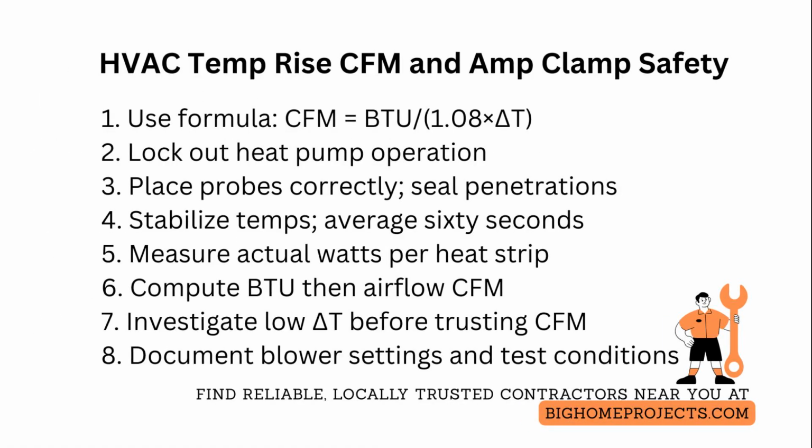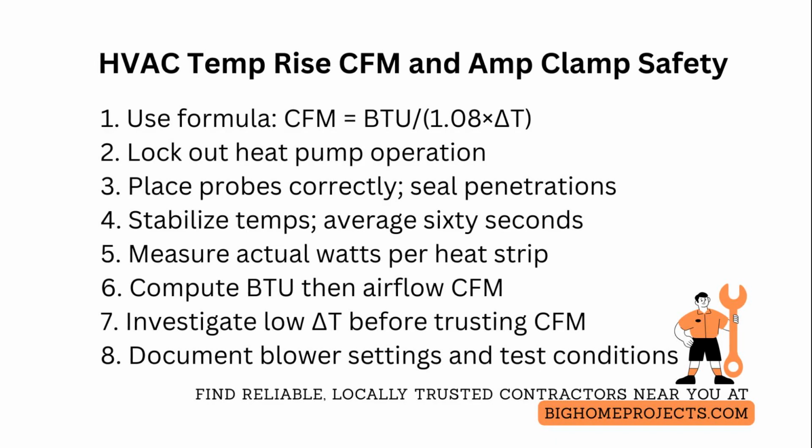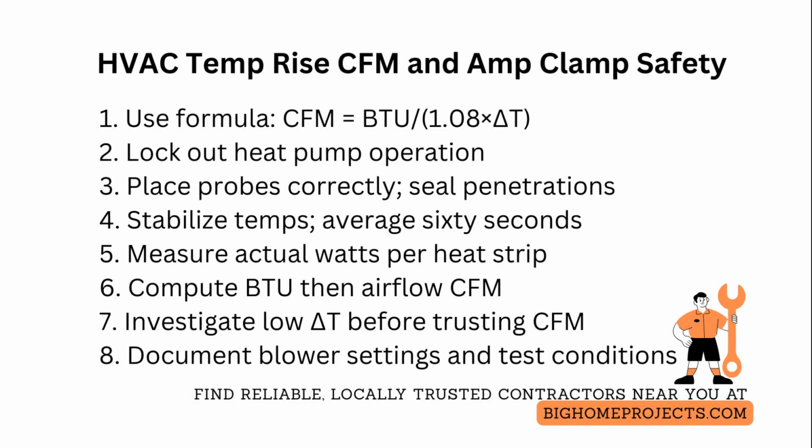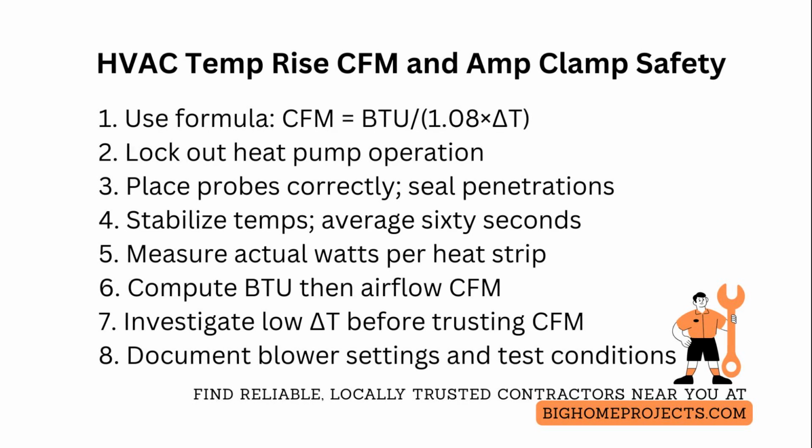For electric heat air handlers, the cleanest method is temperature rise. Cubic feet per minute equals heater output, British thermal units per hour, divided by 1.08 times temperature rise in degrees Fahrenheit, and heater output British thermal units per hour equals measured kilowatts times 3,412.